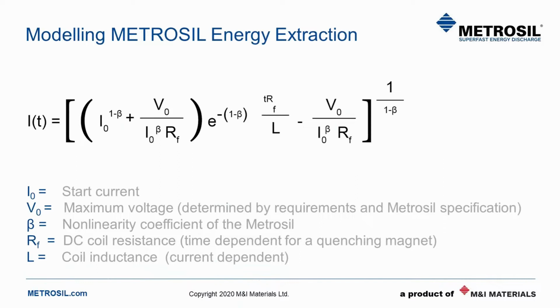The maximum voltage here is determined by the magnet being protected, and then achieved through the type of METROSIL used and its configuration. The beta in this equation, as I mentioned in the last slide, is typically around 0.39. Due to the nonlinear V-I relationship, a small increase in voltage results in a much faster discharge time. So we really want to take the maximum voltage up as high as the magnet will safely allow, to really speed up that discharge.